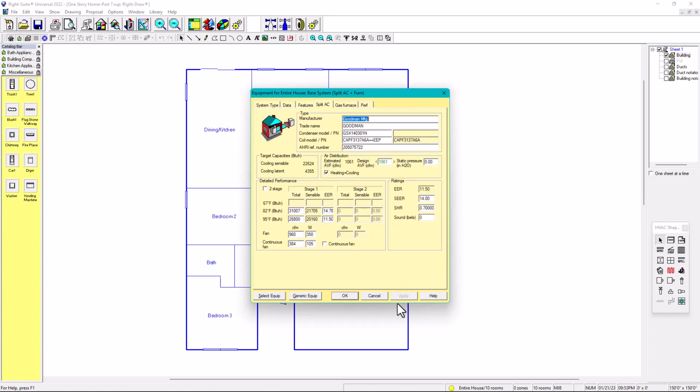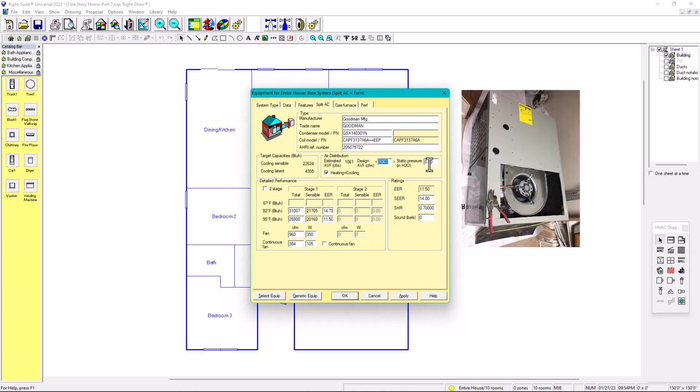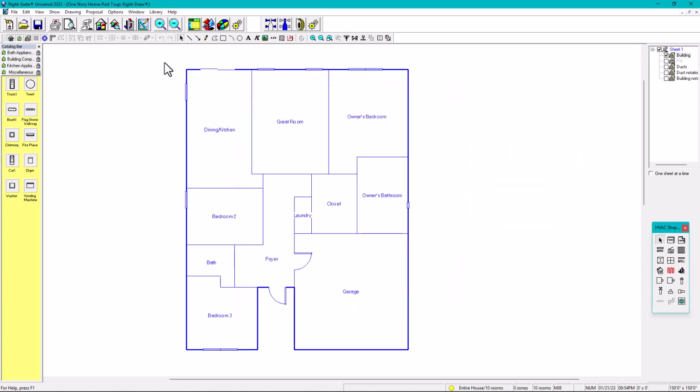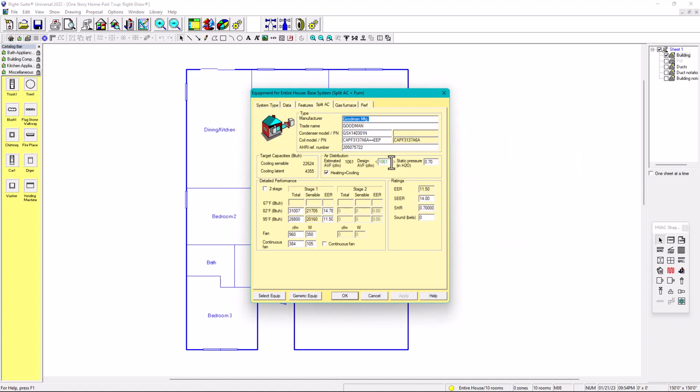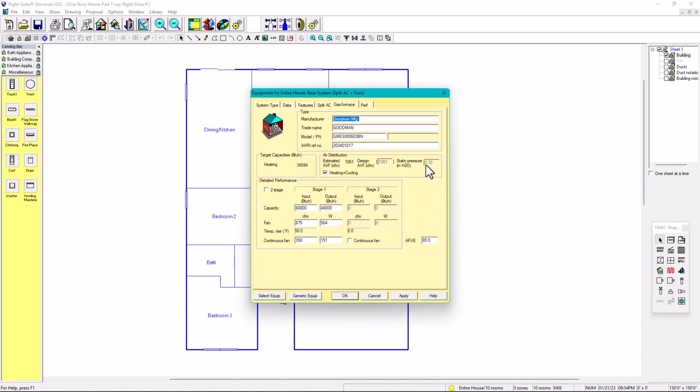And then you hit apply, and then, oh, let's not forget, when you put fan performance, they are married. So the CFM of a fan is married with the static pressure. They don't go alone. They never get divorced. They are always together forever and ever. Therefore, if you talk about CFM, you also have to talk about what the static pressure is. So that's going to be 0.7 static pressure. And then you hit apply. Perfection. Now we have DC apply. There we go. So now we go here. We have the official CFM. And then gas furnace, the same at 0.7 static pressure.